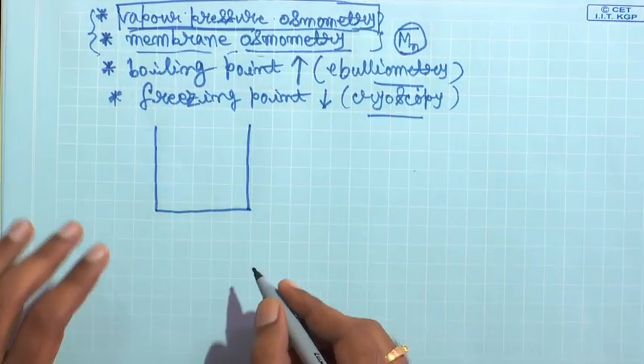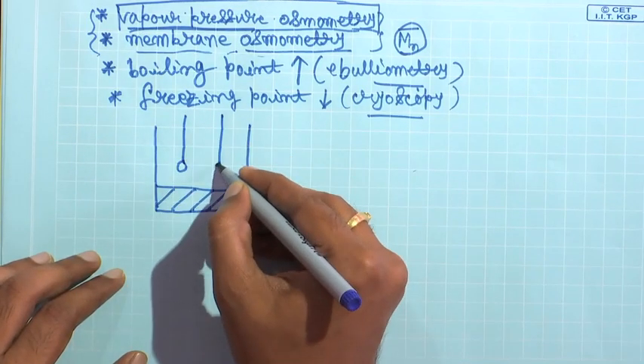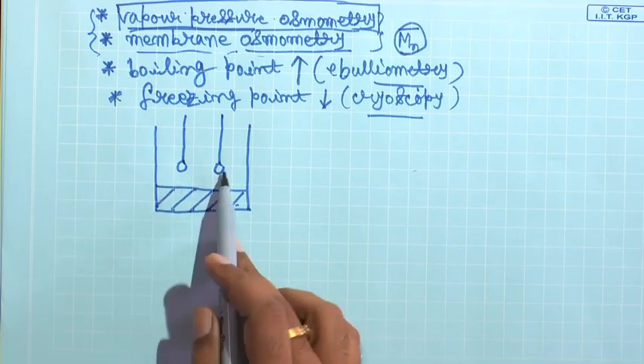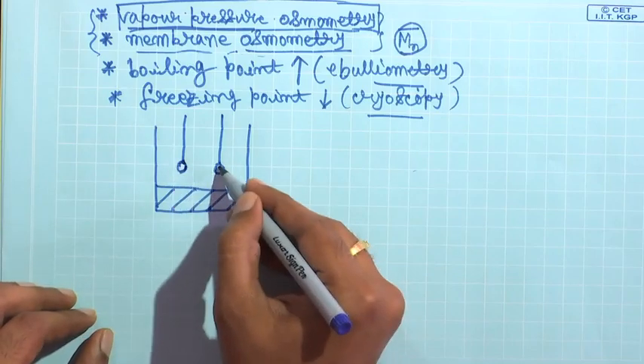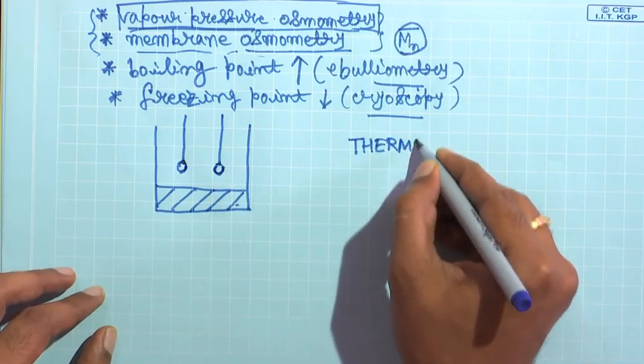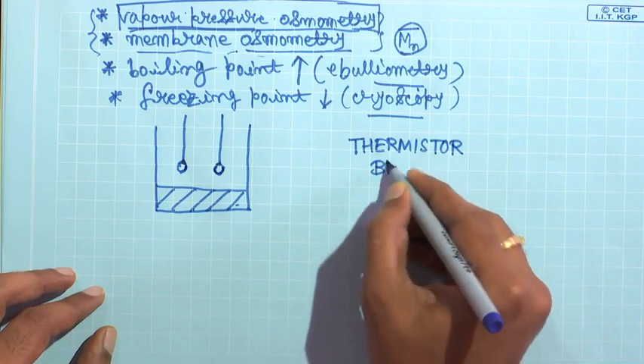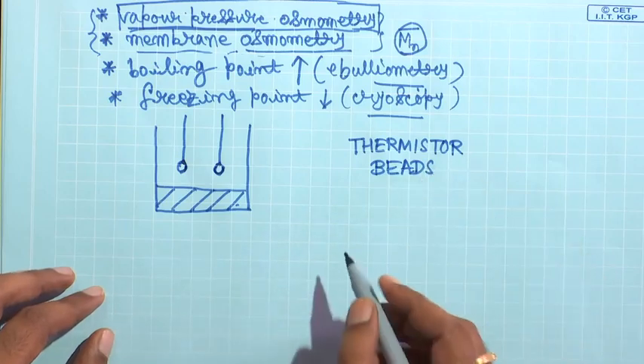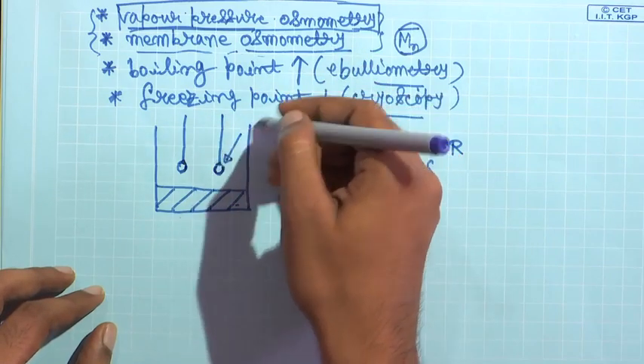Vapour pressure osmometry — the kind of setup that you have looks something like this. You have a chamber in which you have a solvent. You have two thermistor beads that are fixed at a certain position above the solvent. You have a syringe which can put a drop of solvent or solution, and the whole setup is basically temperature controlled — isothermal.